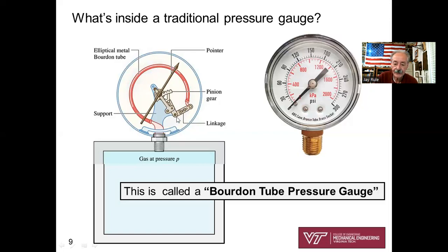So essentially that's the way a Bourdon tube pressure gauge works: you have a high pressure above atmospheric pressure inside this curved tube working against atmospheric pressure outside. And that's why we call it gauge pressure. Do you see that in a lot of ways, it's like a pressure difference. Gauge pressure is a pressure difference higher than the atmospheric pressure. Okay, got it? All right.